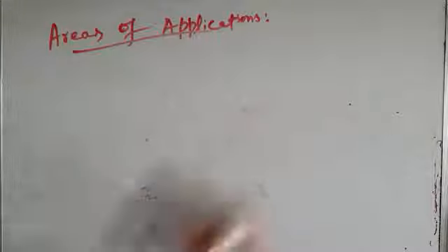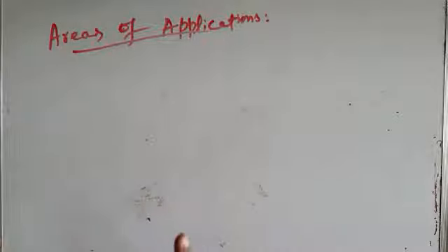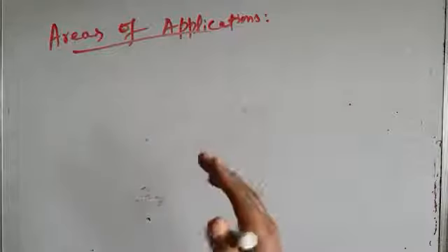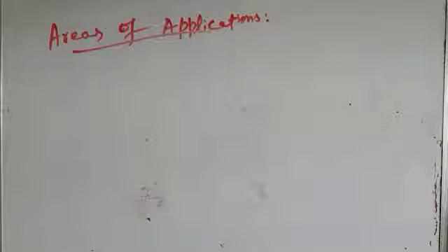You may have to very quickly switch on the SVC and quickly switch it off for one disturbance, and immediately a second disturbance may come after a few cycles. You may have to again switch it on, and so on. So in those applications where quick disturbances are there, an MSC TCR SVC may not be very suitable for voltage control in a system experiencing frequent disturbances.